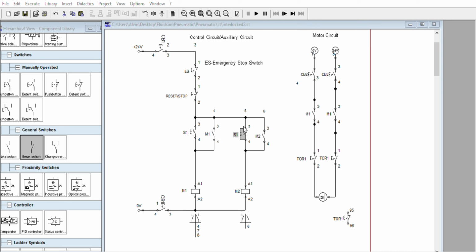And this is, let's say, switch number 2. You cannot label this one as M1 because they don't have the same function. It will not accept it also. Let's say M1. Turn that on. See, there is an error. So M1 should be associated only with power contacts, auxiliary contacts, and the coil of the contactor. So you can use any label other than M1. You can use push button 1, push button 2. Just double click and label. Double click and label.